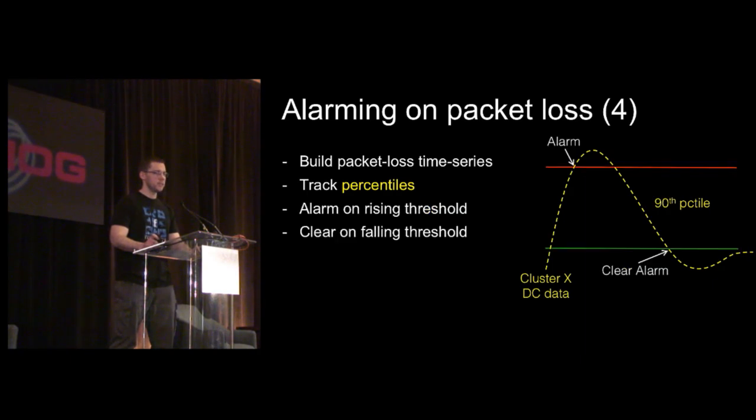For every time series, we define 2 thresholds, rising and falling. This allows you to alarm when the time series crosses the rising threshold and clear the alarm when the time series goes below the falling threshold. The combination of 2 thresholds allows us to eliminate the whiplash behavior which comes from a single threshold only.